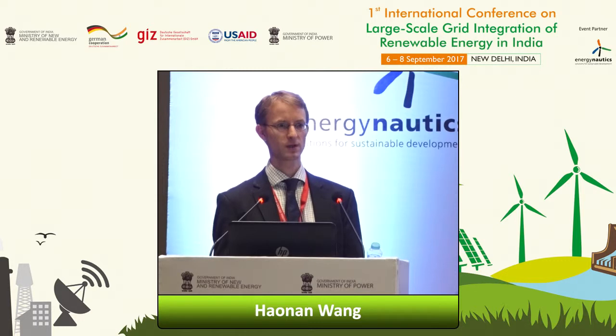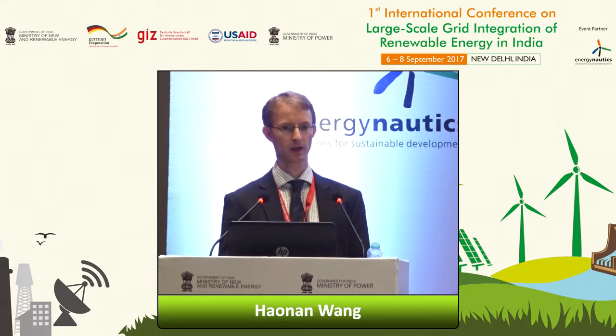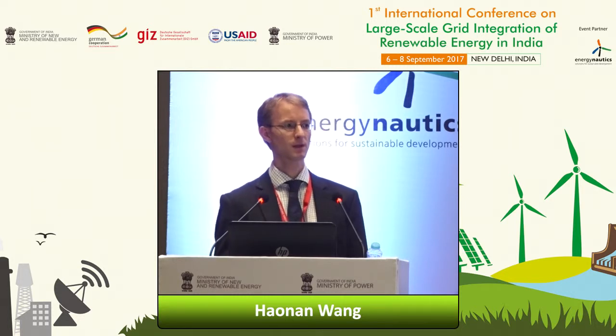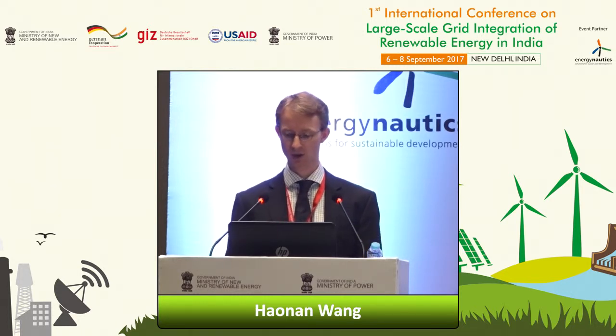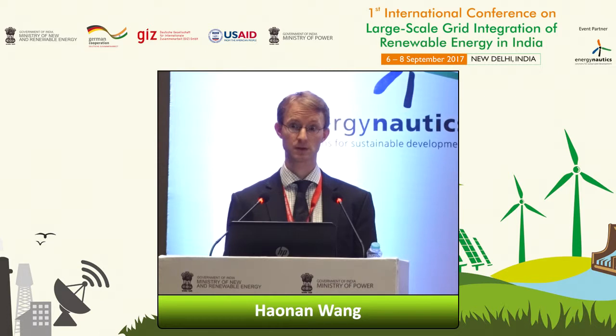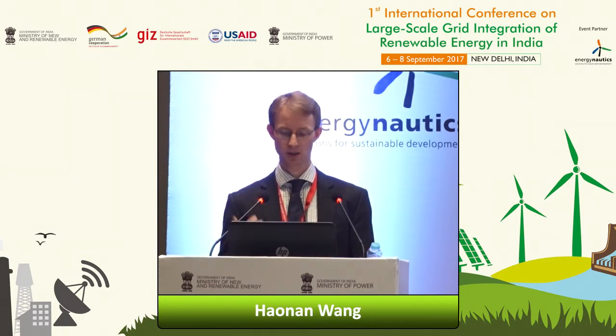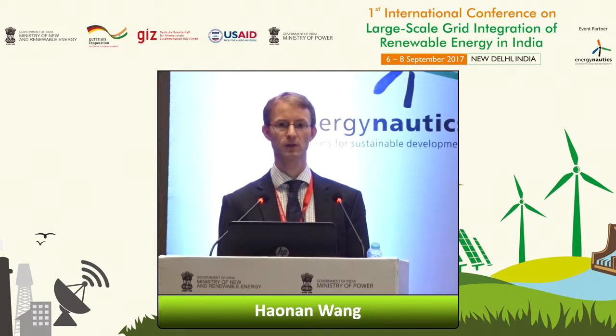In the present standards, those renewable energy systems are not obliged to provide reactive power if they are not providing active power. Of course, they can provide STATCOM functionality, but this is not under present regulation. We see that the blue ones are especially hydro and biomass that is installed there. With PV and wind, we have a significant reactive power flexibility, but not at a very high reliability value. This is an important point, because the question is, can it substitute shunt installations, for example, for compensation? So the question of the reliability requirement at the supply connection point is very important.